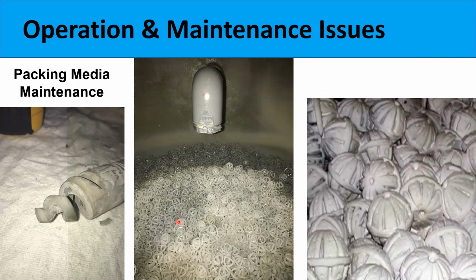Could have had some packing pulled out of the system, and so you get nice, good, clean coverage in the center section of the wet scrubber. But then you can see on these back walls, you're not getting very much scrubbing liquid coverage at all. And you can see the packing is getting really dirty on the outer walls along there. And so it's important to keep this packing media clean.